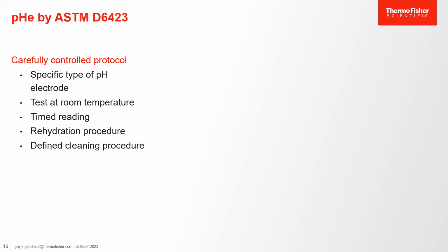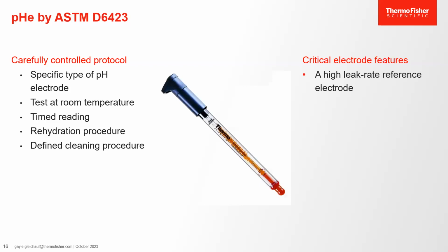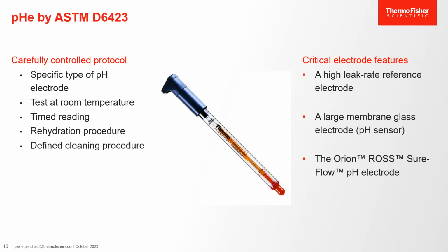The ASTM D6423 pHE method is a pH measurement made under specific conditions, including the use of a specific type of pH electrode, testing at 22 degrees C plus or minus 2 degrees, a timed reading, a rehydration procedure, and a defined cleaning procedure. Critical electrode features for pH testing include a high leak rate reference electrode to minimize junction potential drift, especially in extreme low conductivity solutions like fuel ethanols, and a large membrane glass electrode to perform better and have longer life in alcohol fuels. Per ASTM 6423, the Orion Ross SureFlow pH electrode is recommended as having these necessary features.